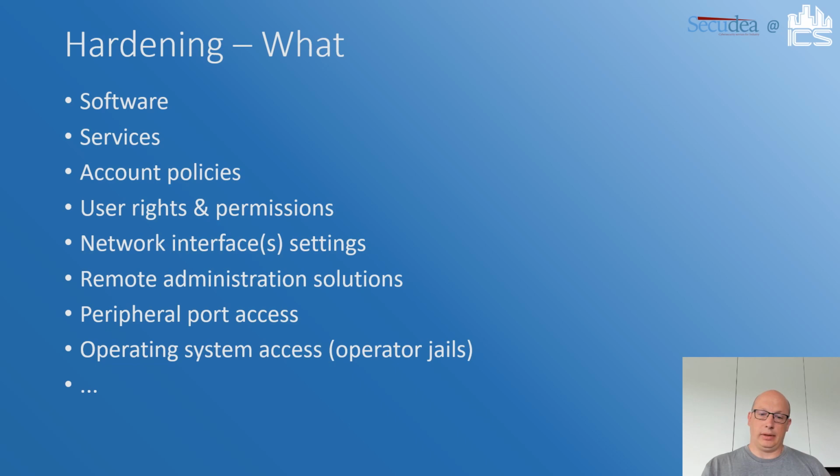So that's why applications should first of all never run with administrator access. For example, WinCC used to need administrator level access, so that was a problem already. But by further protecting the operator jail, by limiting what the operator can do on the operating system, you will further limit possible attack paths into the system.